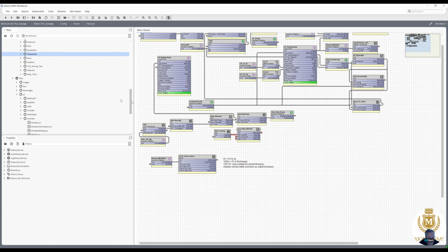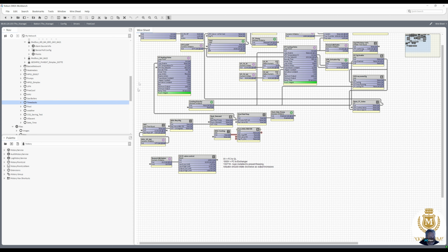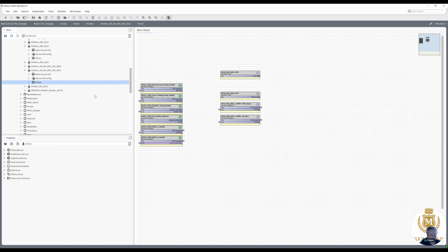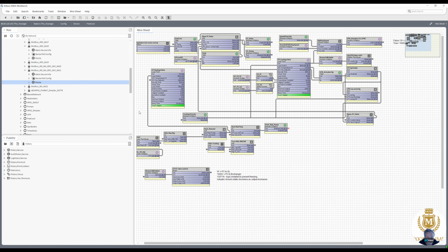Now we had another issue on Modbus module 21, which is there. It had a pump on or something. Radiator pump enable, there you go. Why are we running a radiator?